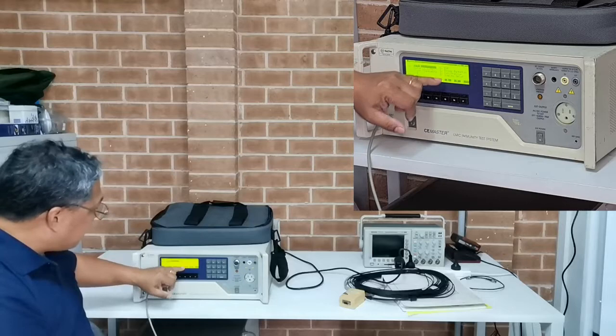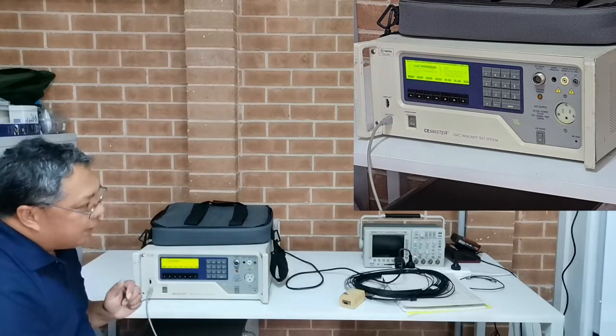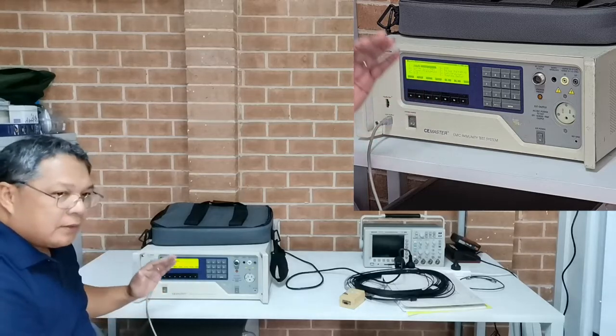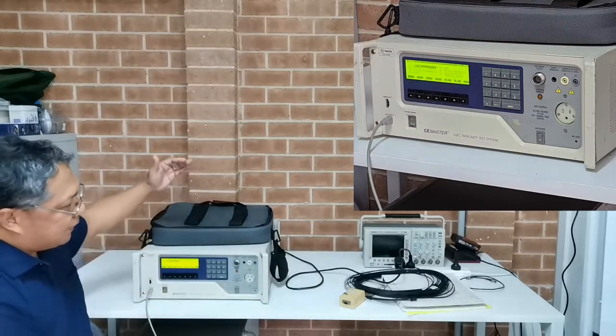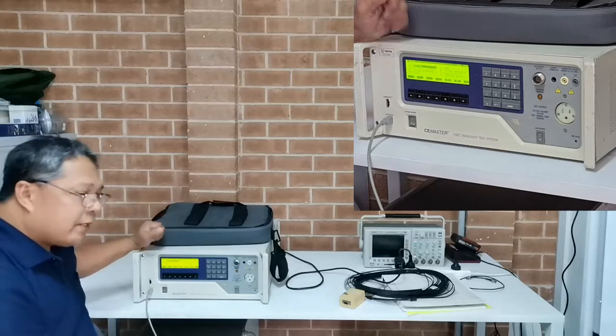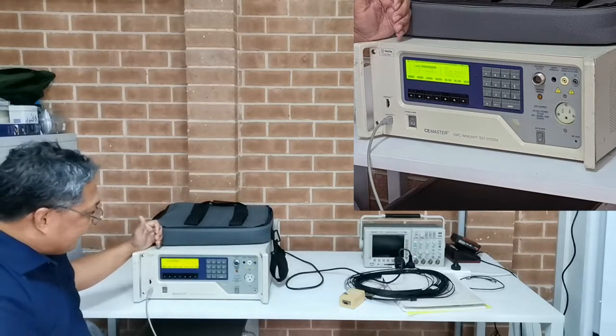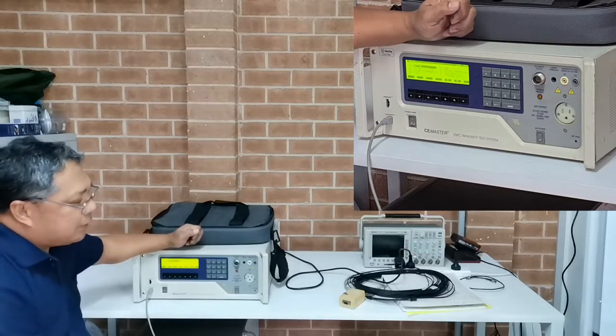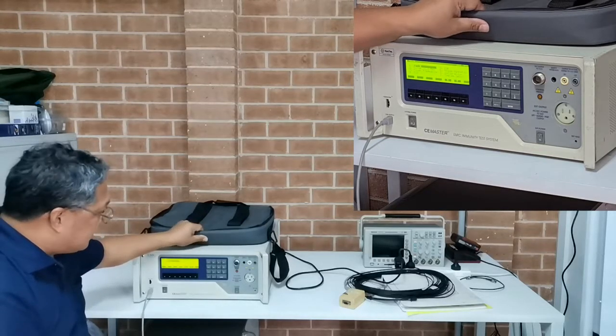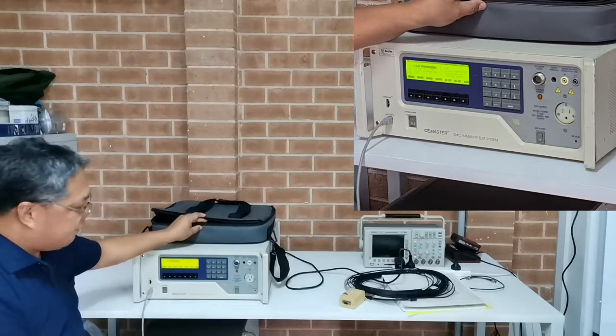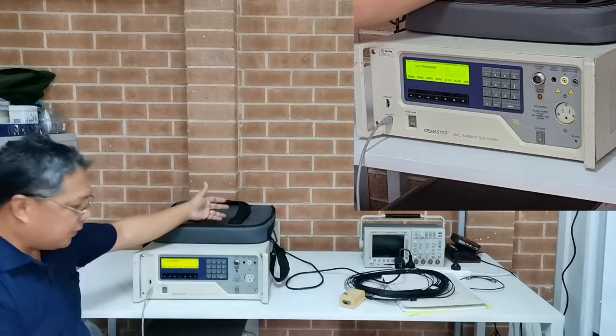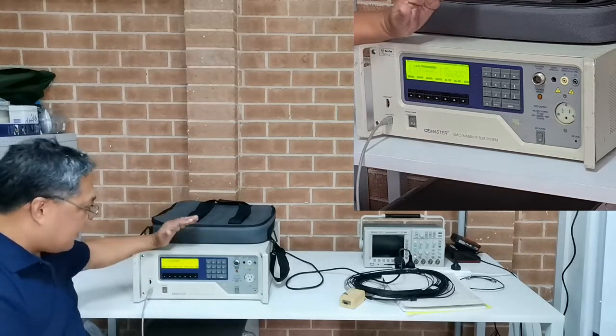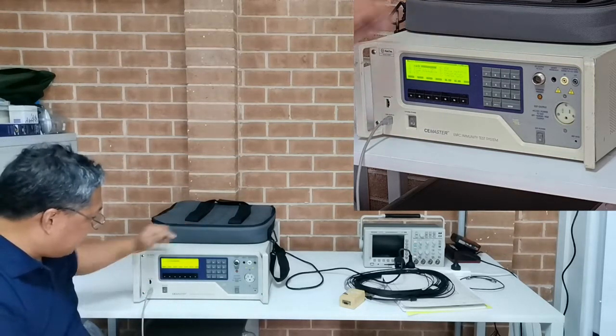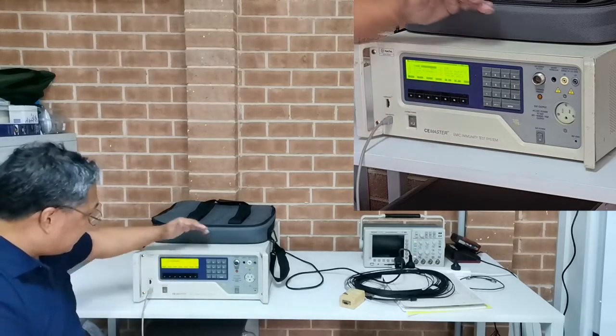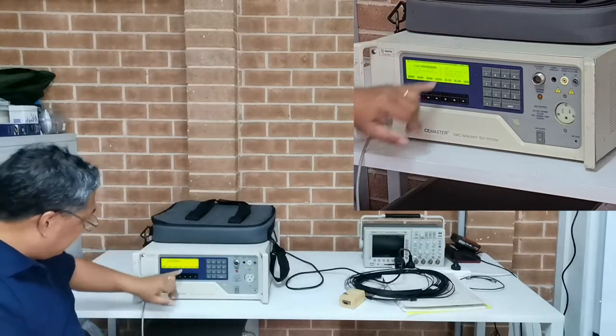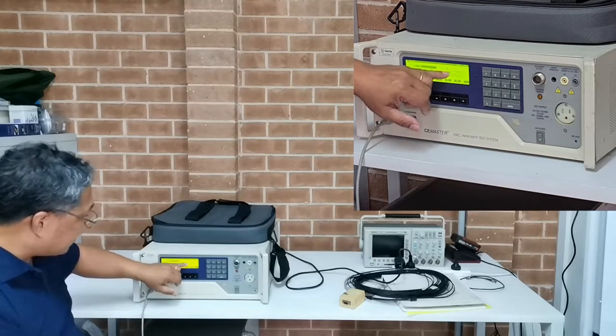The number 5 is the PQF. Unfortunately, I doubt that I can do the PQF on this machine, because the maximum input of the EUT input is only 125 volts, and to do the PQF for Australian units, you need to run at 240 volts, and the PQF happens inside the unit. So at the moment I won't be able to use the PQF. That's called Voltage Dips and Interruptions for 61000-4-11.